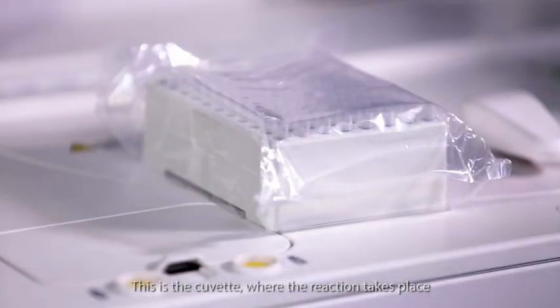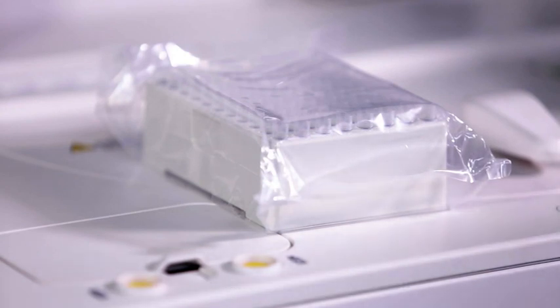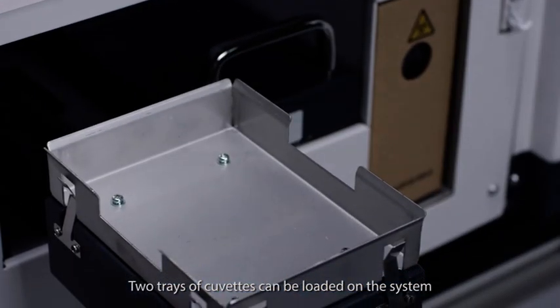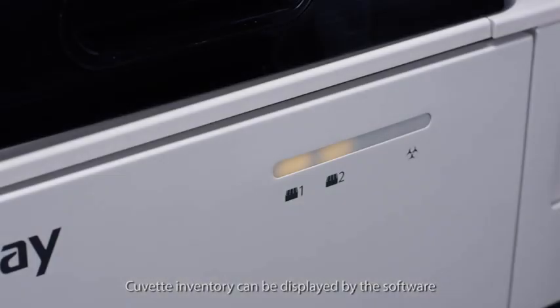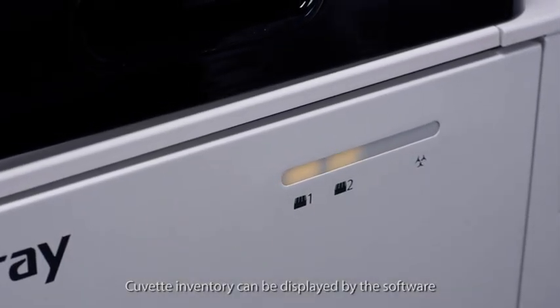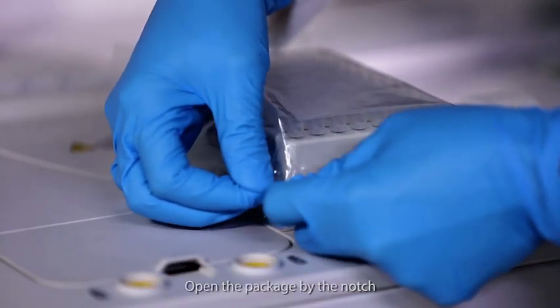This is the cuvette, where the reaction takes place. Two trays of cuvettes can be loaded on the system. Cuvette inventory can be displayed by the software or the indication light. Open the package by the notch. Do not drop or contaminate the cuvettes.